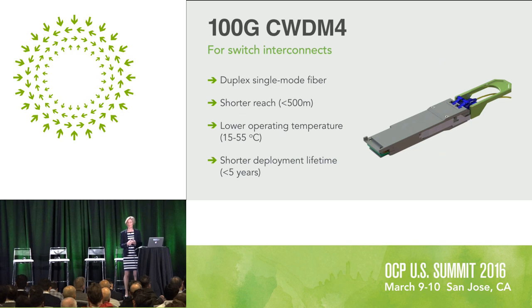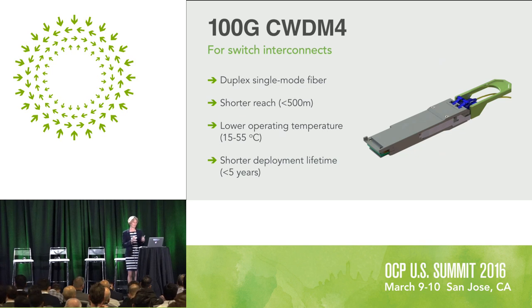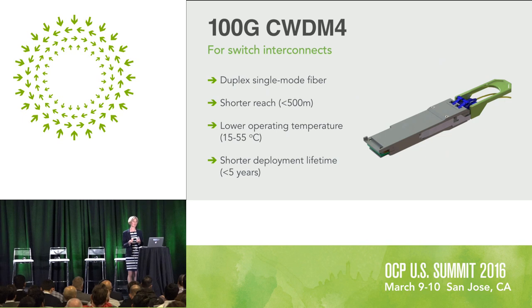The second parameter we tailored to our environment is the operating case temperature. Most of these links go inside a building that Facebook owns, and it can't get too hot inside a data center since real people need to go in there occasionally. Having a case temperature range of 15 to 55 degrees C is something we maintain anyway — so why not specify that from the beginning? Since most parameters are temperature-dependent, this significantly reduces the parameter space that the product needs to perform over.